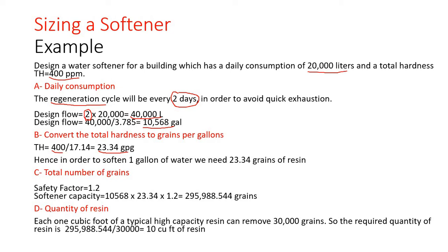Third, we need to know the total number of grains. We will choose a safety factor of 1.2. Therefore, the softener capacity will be 10,568 times 23.34 grains of resin, times the safety factor of 1.2, giving us the answer in grains. We know that each cubic foot of a typical high-capacity resin can remove 30,000 grains, so the required quantity of resin will be the total number of grains divided by 30,000. We need around 10 cubic feet of resin to soften our water.